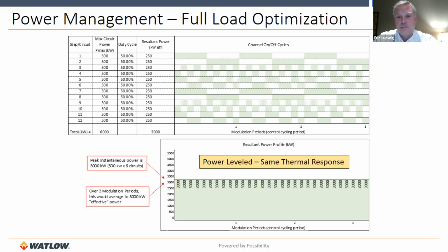So we don't get these very large swings in power within the grid. You can see this has been fully optimized. This is an ideal optimization scenario where all 12 circuits are working together. They are actually talking to each other through the SCR algorithms, and their on-off times are synchronized. You see the average power on the resulting graph below is still your 3 megawatts, but it's all leveled now.